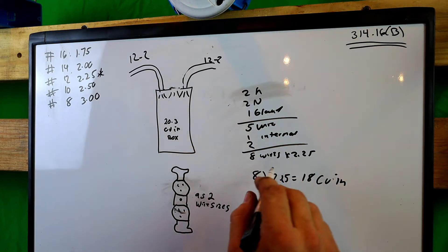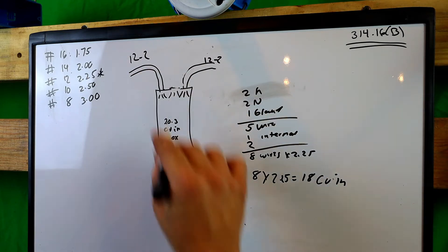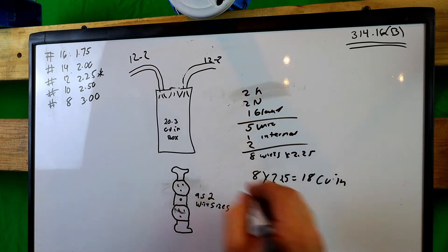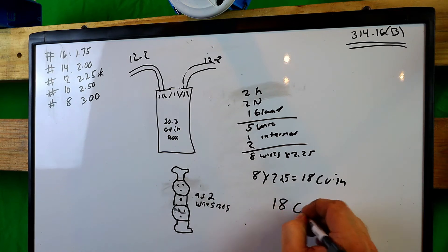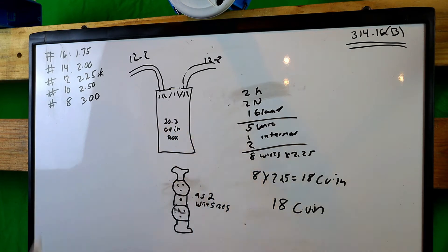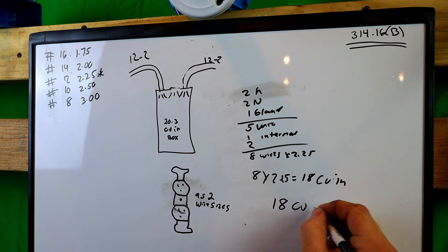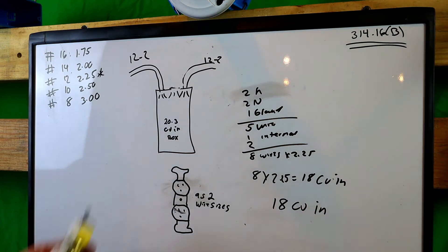All right. Here's where we're going to start. So we know that our box fill with the wires we have in it and the yoke receptacle, we have at 18 cubic inches. Now we know that our box in question is 20.3 cubic inches. So we are completely in line with this. That looks like it's Koonin. Let me, let me fix that. Cubic inches. There we go.